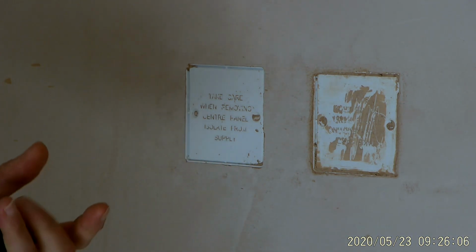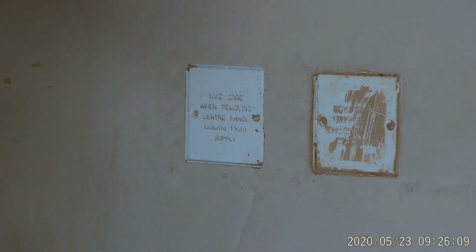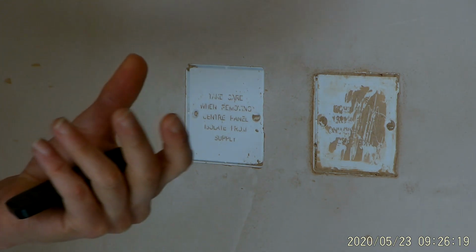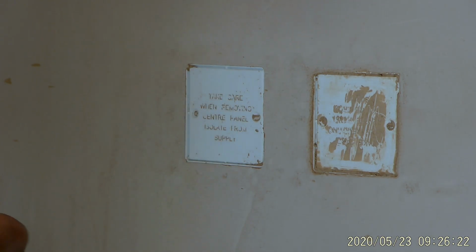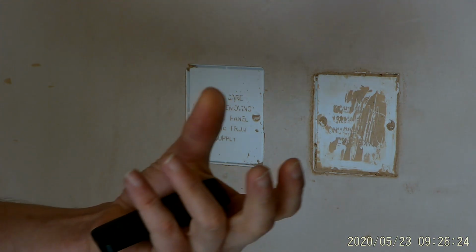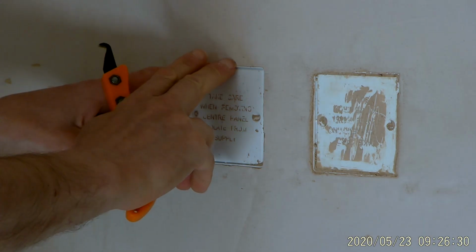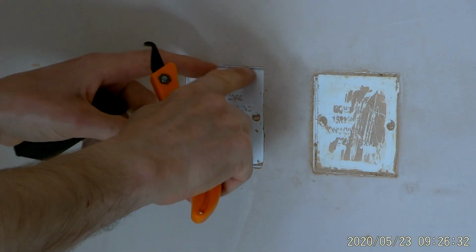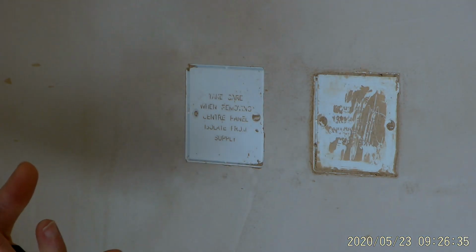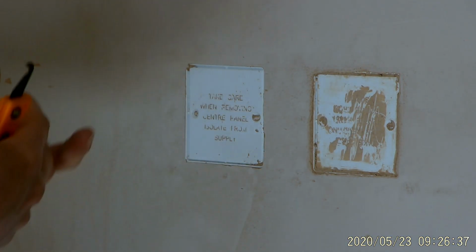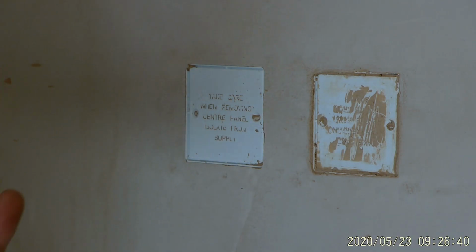The other great thing about this is, when I was doing my first fix, before I walk away, I always do some testing, R1, R2 testing, and that way I can make sure that all my circuits are complete and tested up to that point. So if I walk away and a socket or circuit gets damaged and I've lost continuity, I can say that that wasn't like that when I left. Before I leave, I used to get my apprentices to go around and strip all these switches and sockets. So when we came back to do our second fix, all of that was done. All we had to do was screw the accessories on. So these products are fantastic for that.